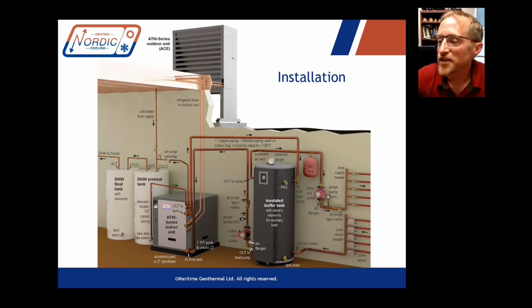So here's a slide I just added today because for some reason I didn't have it in previous presentations, but this is if you had a system installed, this is what it might look like. So the indoor unit of the heat pump is here. You can see it's connected with refrigeration tubing through the outside wall to the outdoor unit. And that's the back of the outdoor unit since the fans are facing away from the house. The maximum line set length is 70 feet, so you have to plan a location where that is possible. The indoor unit comes charged with enough refrigerant for 20 feet of line set. So if you have more than that, you can add a little bit of refrigerant to make up for that longer line set.